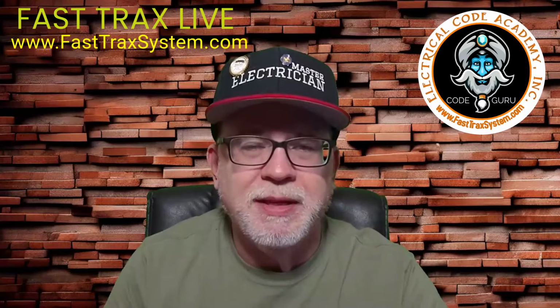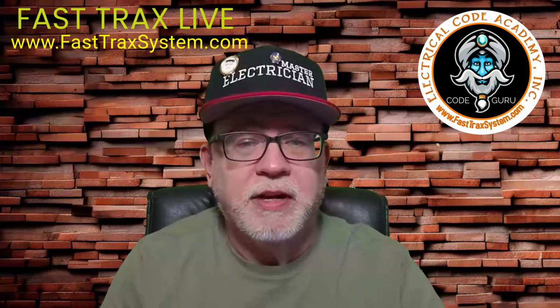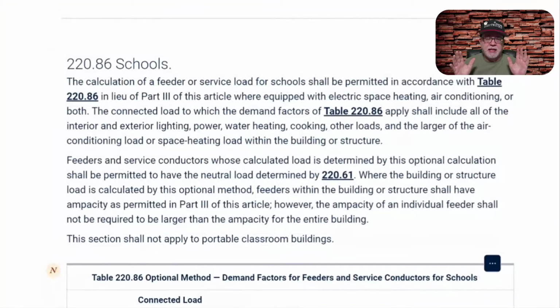So what we're going to be looking at is the NEC first. Here's the National Electrical Code, and we'll explain it quickly before we look at an example and work it out. When you're doing a school calculation, we're talking about the entire school, not portable classroom buildings, which are not part of the overall school. We don't lump them in because in this optional method we're not taking lighting, for example, at 125% for continuous loads. We're just lumping values together at their total connected load value and using that to apply some demands.